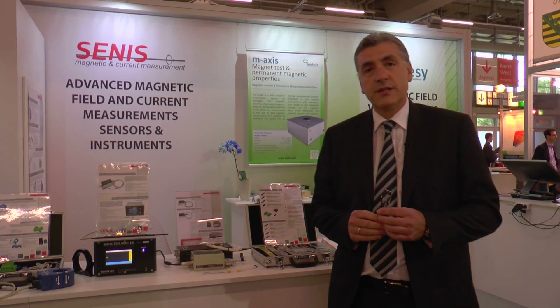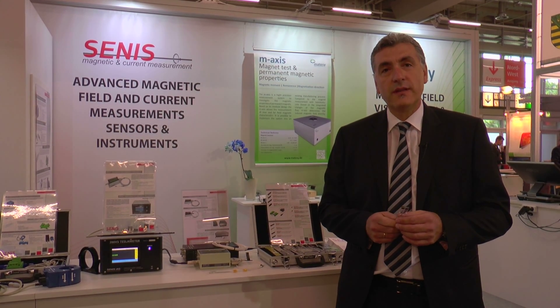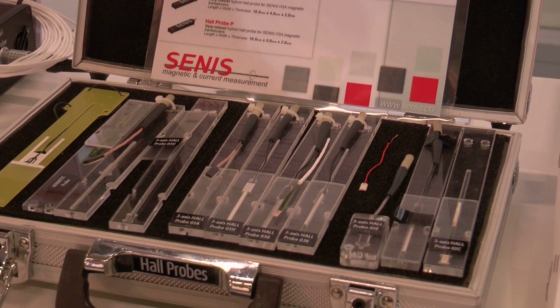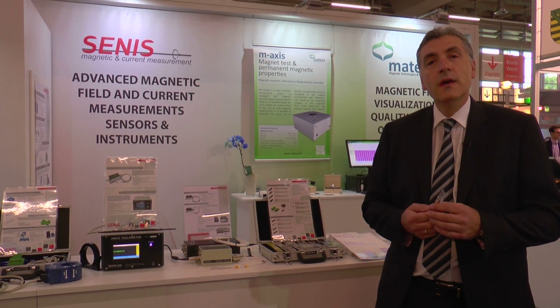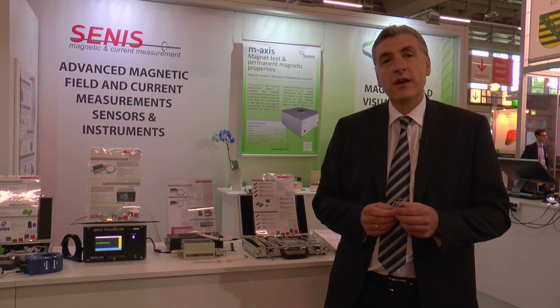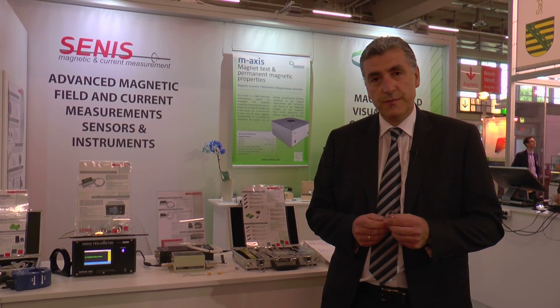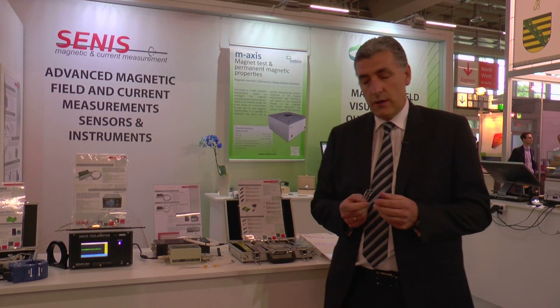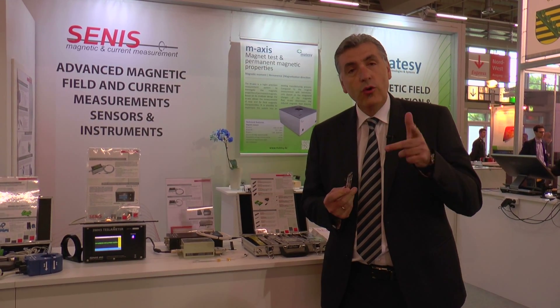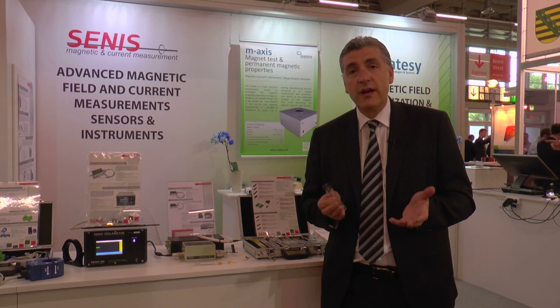The heart of our magnetometers is the hall probe. SENIS has developed a patented solution of integrated 3-axis hall probe. This is a single silicon chip that integrates vertical and horizontal hall devices, a temperature sensor for temperature compensation, and an electronic circuit spinning current for offset noise and planar hall effect cancellation. The vertical and horizontal hall devices are integrated on that single chip in a way that it measures all three components of the magnetic field in a single spot that is less than 100 micrometer square.